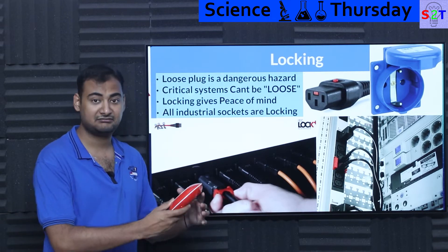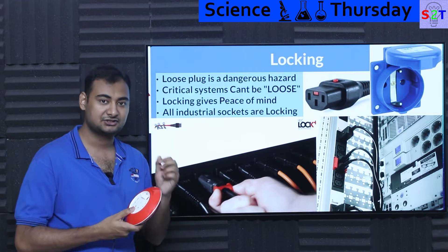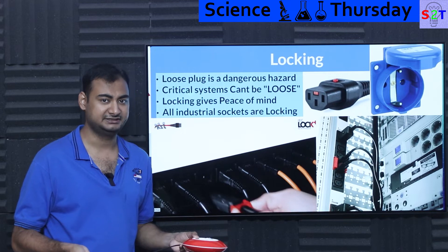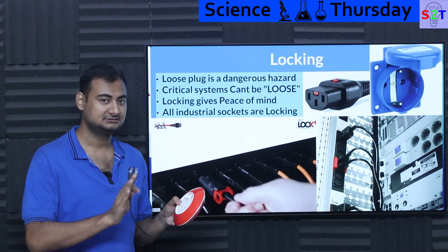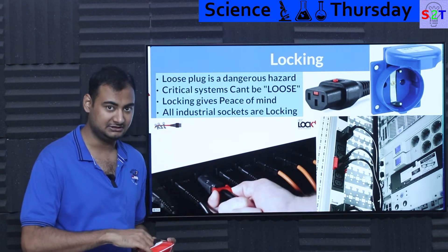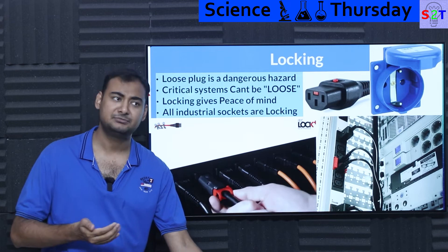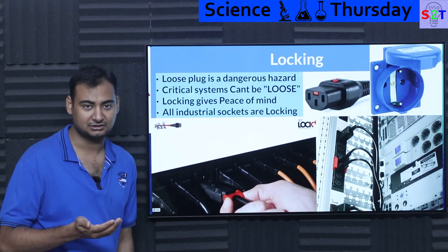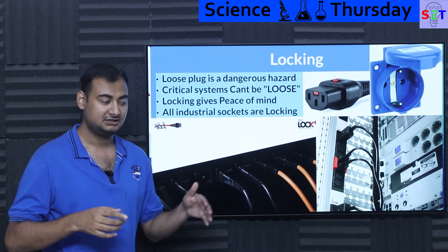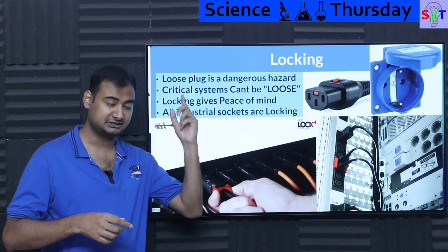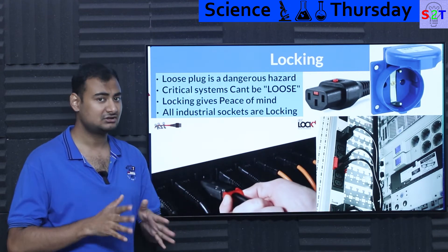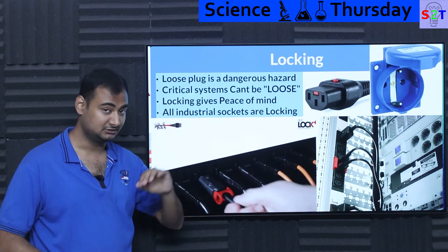Loose plugs are not acceptable. That's why any serious standards association will never allow universal plugs in critical locations like hospitals. You need dedicated male and female connectors to work reliably. For low-current loads like 1 amp, almost any loose fitting will work, but at 10 amps — especially with surge loads from universal motors or induction motors with high starting current requirements — a loose plug will simply melt.